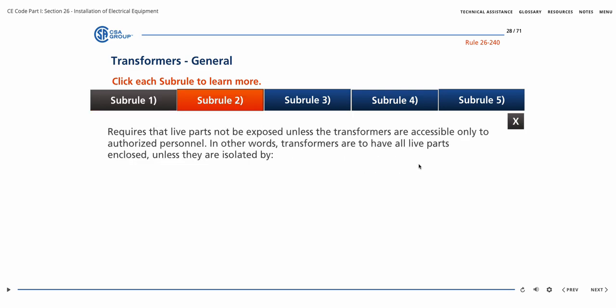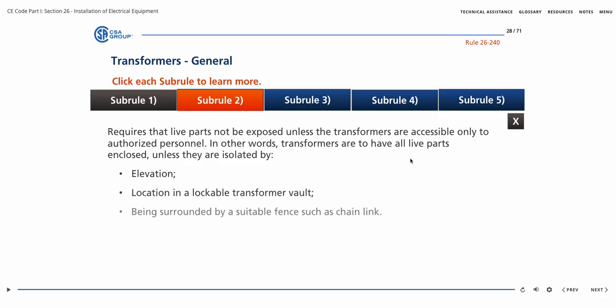Subrule 2 requires that live parts not be exposed unless the transformers are accessible only to authorized personnel. In other words, transformers are to have all live parts enclosed unless they are isolated by elevation, location in a lockable transformer vault, or being surrounded by a suitable fence such as chain link.